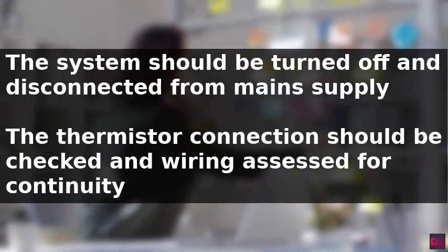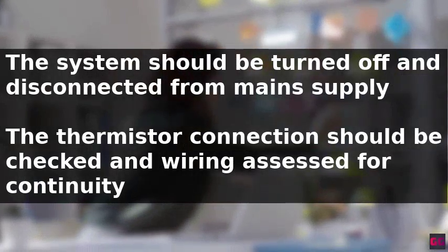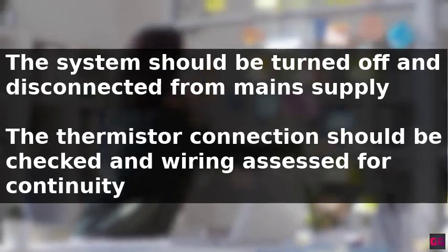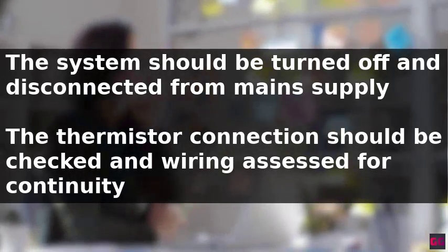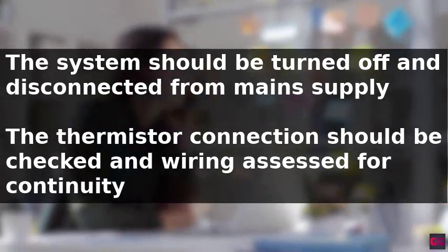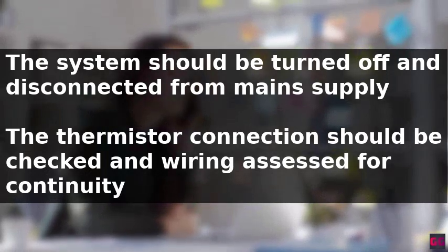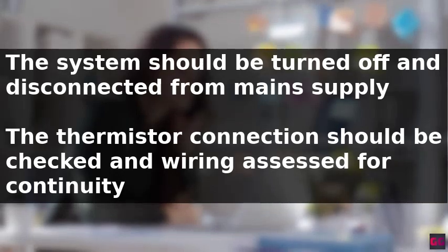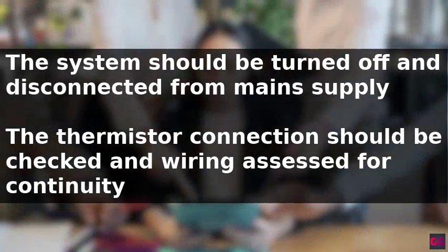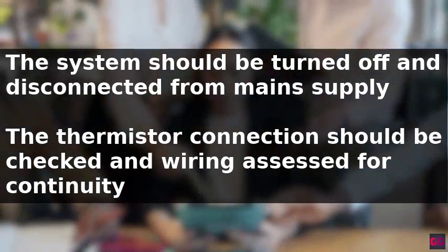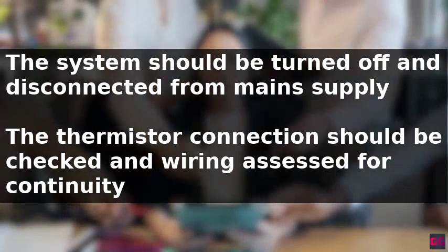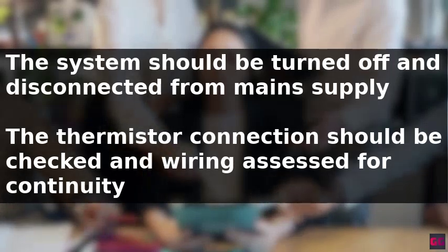To resolve this error, it is essential to start by checking the thermistor connection. The system should be turned off and disconnected from the mains supply, allowing access to the outdoor unit's thermistor. The component's wiring should then be assessed for continuity, and any faulty connections should be repaired or replaced as necessary.